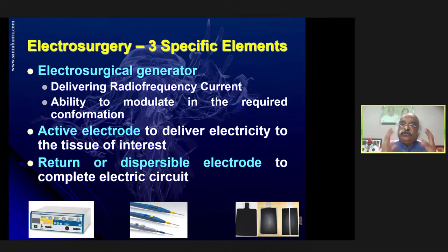I have already told you, it is a source delivering radio frequency alternating current. And second, the generator is so designed that it obtains the household 60 Hz and converts it into about 300 to 5,000 kilohertz, with the ability to transfer it to the electrode. It should also have the ability to modulate in the required conformation according to the needs of the surgeon.